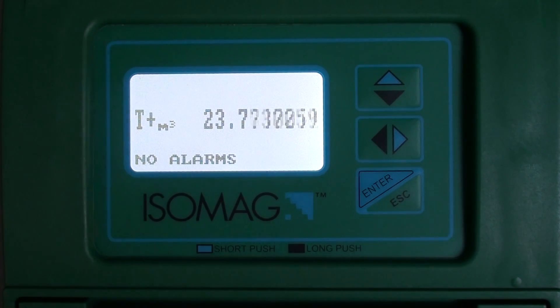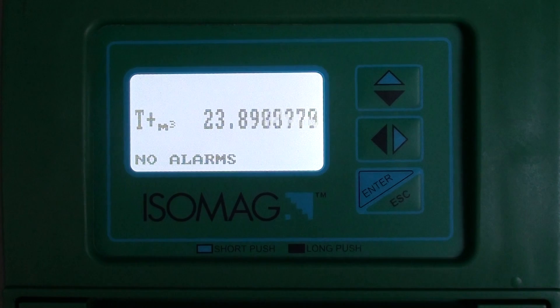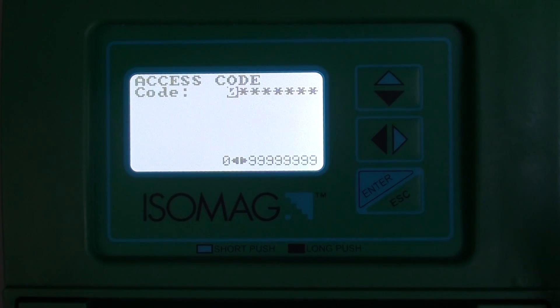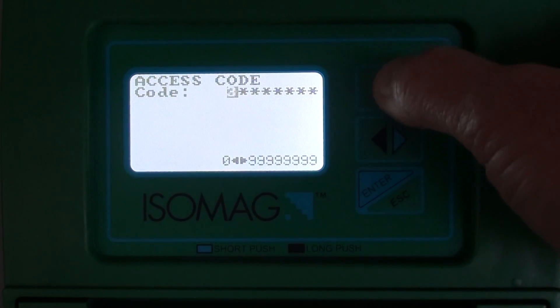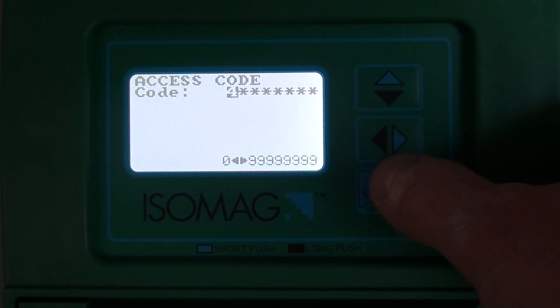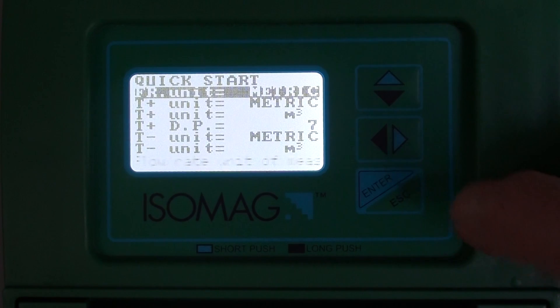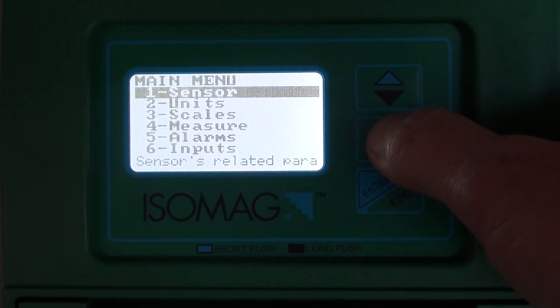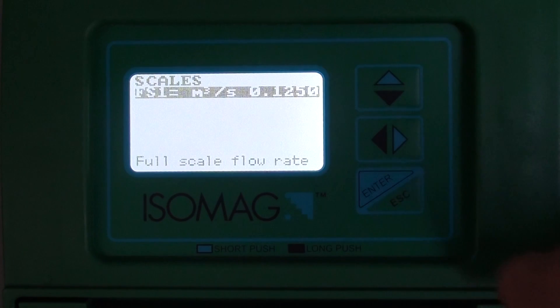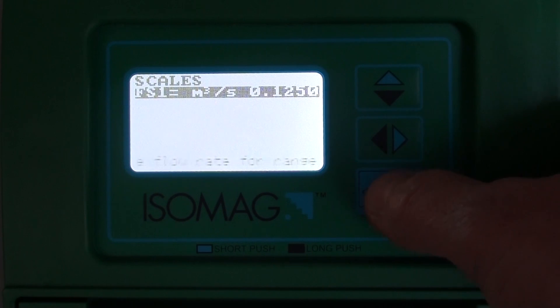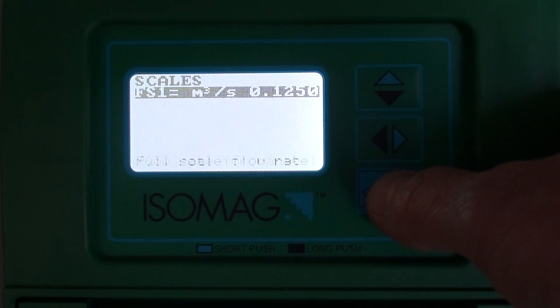We may want to set the 4-20 milliamp output of the flow meter. To do this, we need to set the unit of measure and the 20 milliamp range of the flow meter. To do this, we go to the scales menu to ensure that we have the correct unit of measure for the 4-20 output.